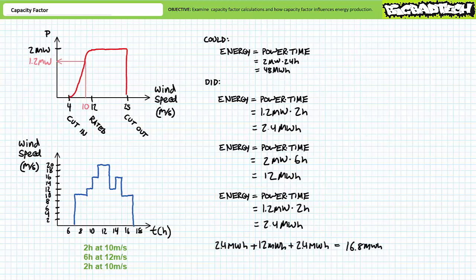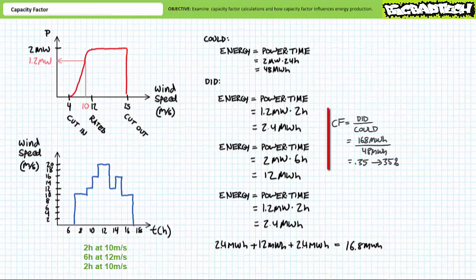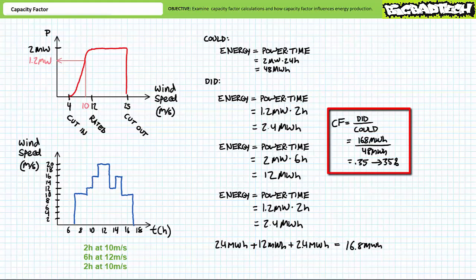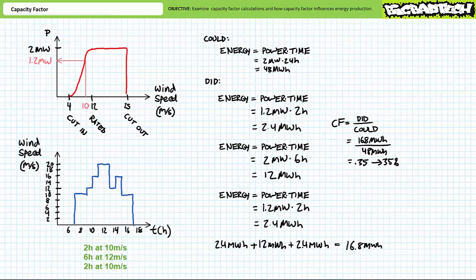In summation, the turbine produces 2.4 megawatt hours plus 12 megawatt hours plus 2.4 megawatt hours or 16.8 megawatt hours of energy in total. What's the capacity factor of this turbine if it could produce 48 megawatt hours of energy a day, but in reality, it only produces 16.8 megawatt hours of energy. 16.8 megawatt hours over 48 megawatt hours yields a capacity factor of 35% as previously. This is to imply that although the turbine experiences periods of variable output for a variable length of time, in this case two hours at 1.2 megawatts, six hours at 2 megawatts, followed by another two hours at 1.2 megawatts, ultimately appears as if it was operating at full capacity for 35% of 24 hours or 8.4 hours at 2 megawatts.